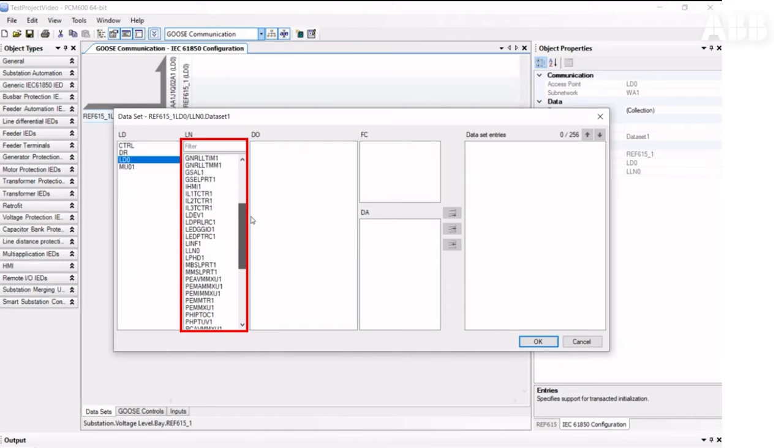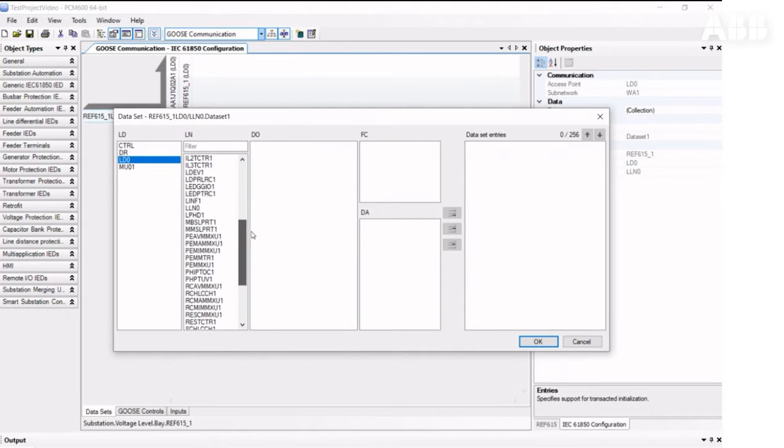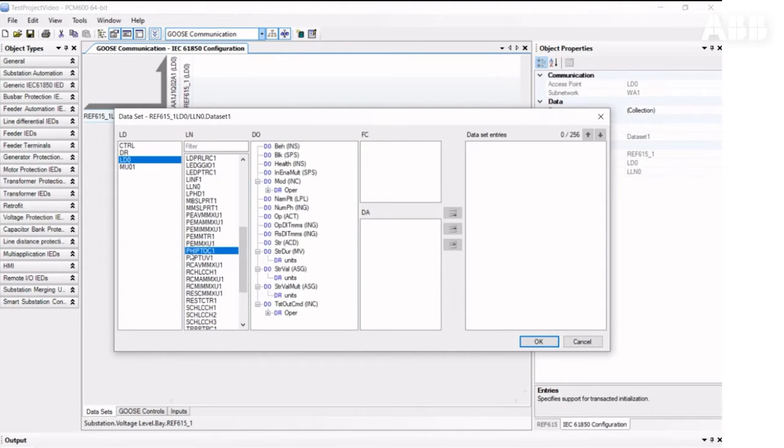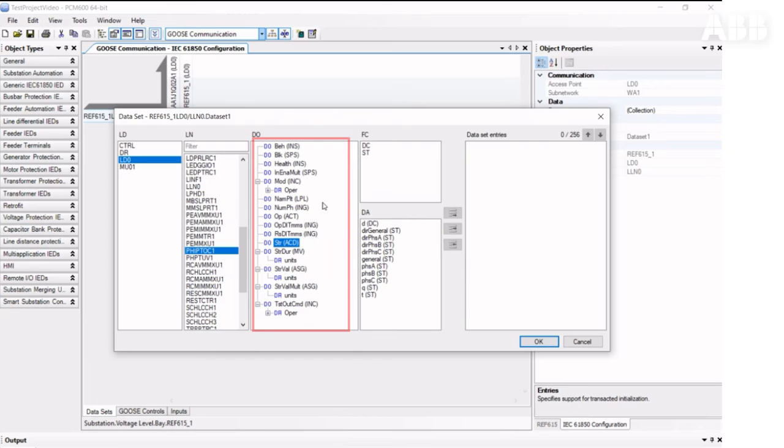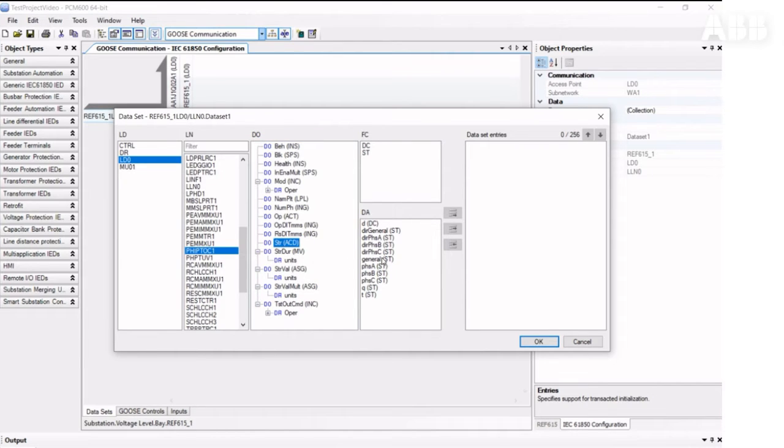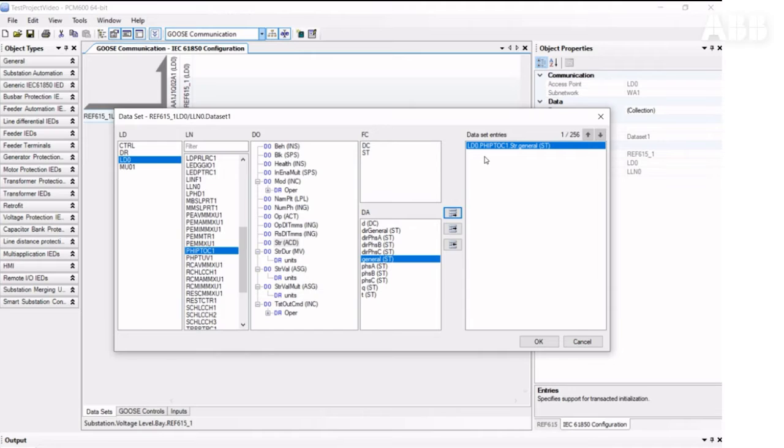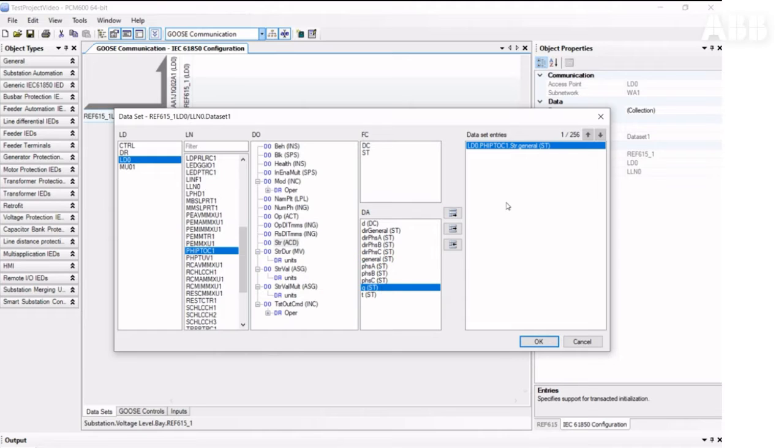Then correct Data Attributes for startup current, which is STR General, and this button will assign the element to the dataset. According to the IEC-61850 standard, the status signal must always be followed by a quality signal, so we assign the quality signal as well, and click OK to save the changes.